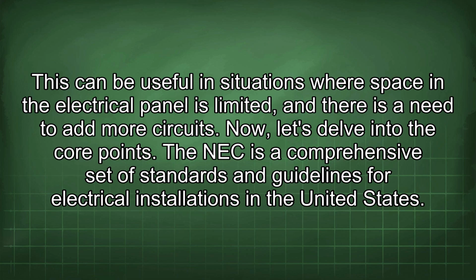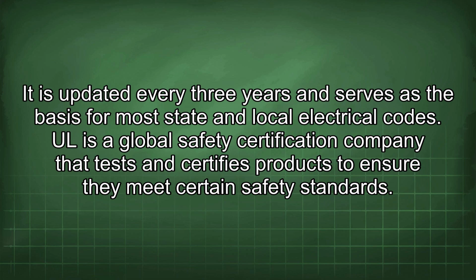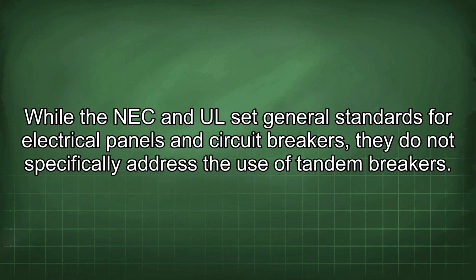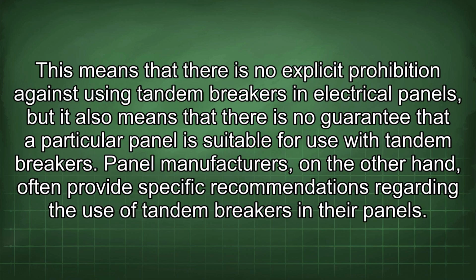The NEC is a comprehensive set of standards and guidelines for electrical installations in the United States. It is updated every 3 years and serves as the basis for most state and local electrical codes. UL is a global safety certification company that tests and certifies products to ensure they meet certain safety standards. While the NEC and UL set general standards for electrical panels and circuit breakers, they do not specifically address the use of tandem breakers. This means that there is no explicit prohibition against using tandem breakers in electrical panels, but it also means that there is no guarantee that a particular panel is suitable for use with tandem breakers.